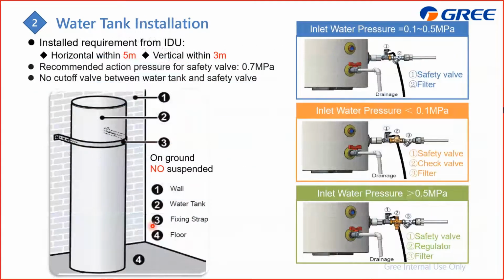And then the next is how to install the water tank. First is the distance to the indoor unit or to the monoblock outdoor unit. This is horizontal within 5 meters and vertical within 3 meters. And also when you install the water tank, it is prohibited to install it on a suspender, which means it is required directly on the ground.